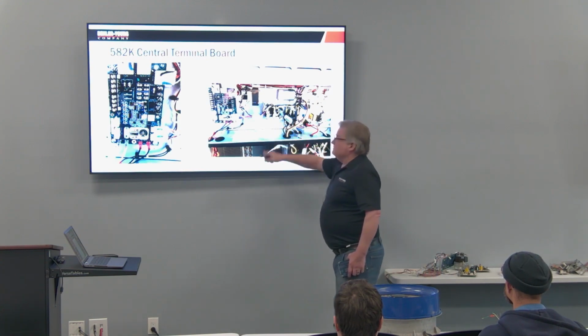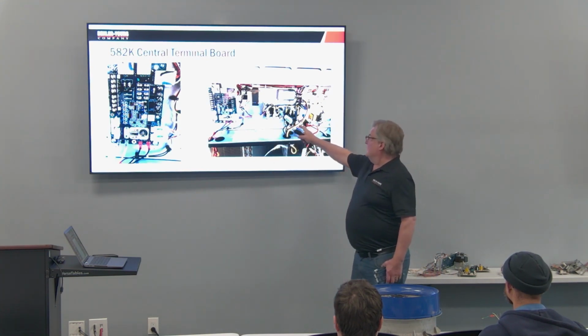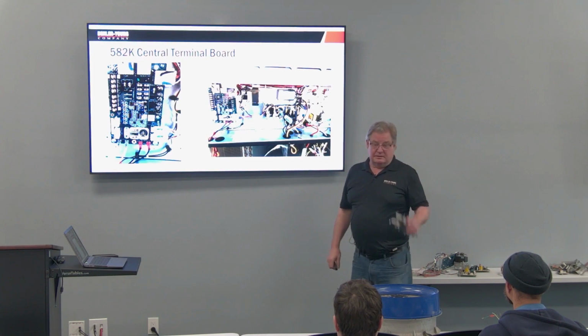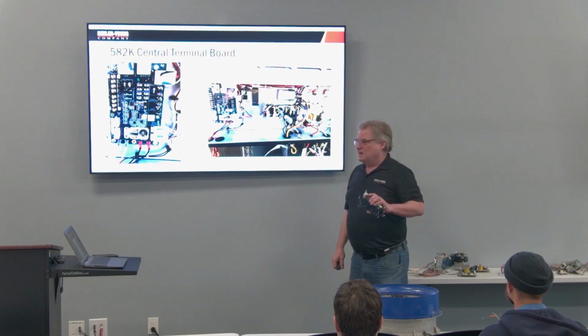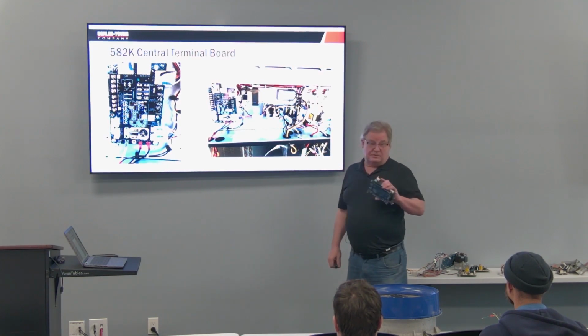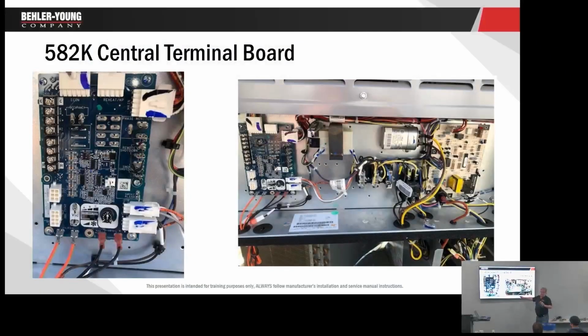Something that's also missing from this compartment is that there's one contactor, right? And this is important to know when we start talking about why we're frying motors. There's no contactor for the blower motor. That's the compressor contactor. All right. Why is that?